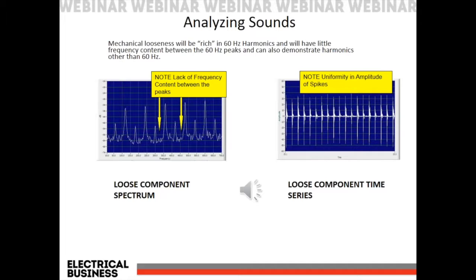So right now we know it's a mechanical vibration, but where is it coming from? It's the 120s. Those 120s that are actually higher than the 60 hertz are the clear-cut factor to tell us where it's coming from. In fact, the 120s are a clear indication that this is happening at the core of a transformer. So this actually is a loose winding happening in the transformer, a dry transformer, obviously. I know this is probably not as clear as it could be if I could sit down with anybody for hours to talk about this. But the lack of frequency content in between these peaks, and the harmonics there, indicate that it is a mechanical issue rather than an electrical emission.